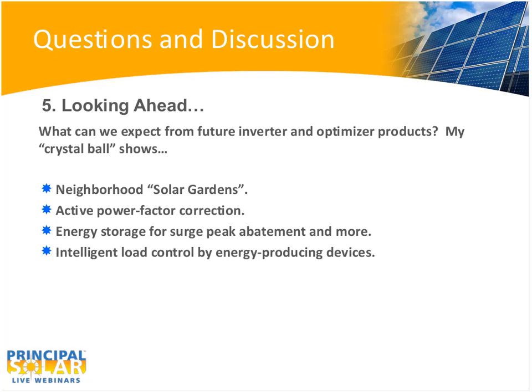You work in a large industrial building, you've got a couple 200 horsepower compressors that want to kick on at the same time. Those who've worked in manufacturing or industrial sectors know many of those industrial meters have a peak demand needle or some other indicator. If you spike way up even momentarily, so does your bill for the next several months. If we have a way of controlling the peak demand consumed, letting loads come on slower, maybe only one at a time, or commanding inverters into a momentary grunt mode to decrease that peak, it benefits the customer substantially. So I see intelligent load control by energy producing devices, and these neighborhood solar gardens, happening in the next 1 to 5 years.